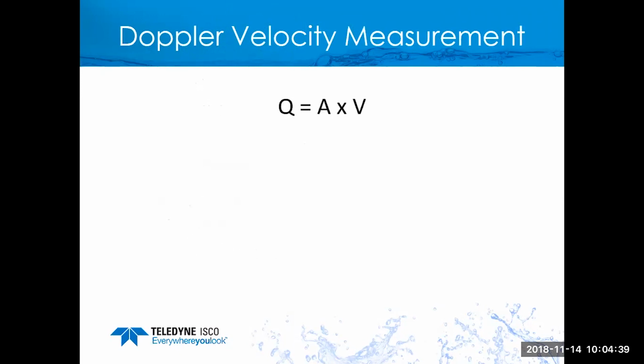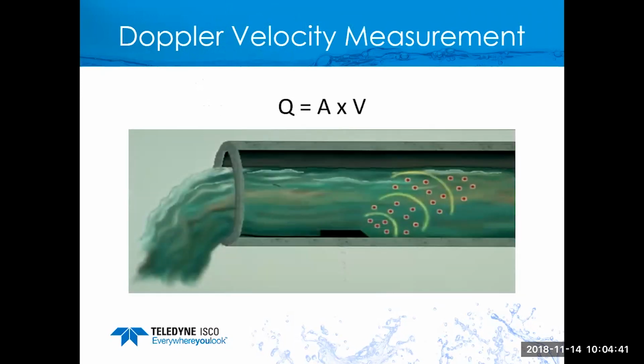So let's give you a little visual of what a sensor looks like when it's the traditional one. There's a sensor on the bottom of the pipe, and it's measuring the level using a pressure sensor. It transmits an acoustic signal out the nose to measure the Doppler shift. We know the frequency transmitted, we know the return frequency, and we can calculate the velocity. These are very, very popular in the industry, mainly for inflow and infiltration studies. There are thousands of these in service.